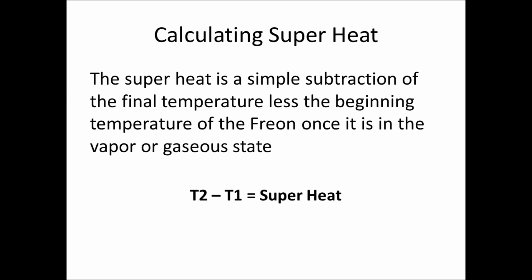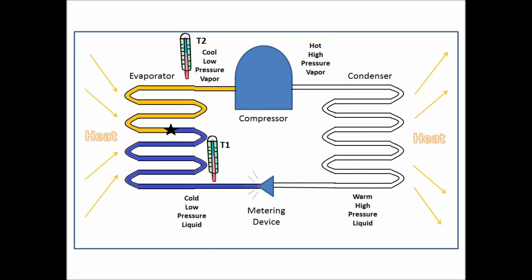So, calculating superheat. Superheat is just a simple subtraction: the final temperature less the beginning temperature, or T2 minus T1. This is your superheat across the evaporator coil. T1 is the liquid temperature of the freon entering the evaporator coil, and T2 is the gas temperature leaving the evaporator coil.